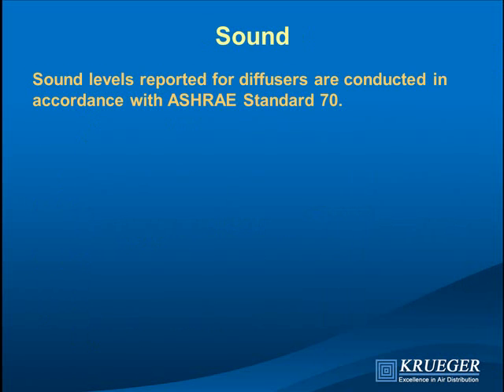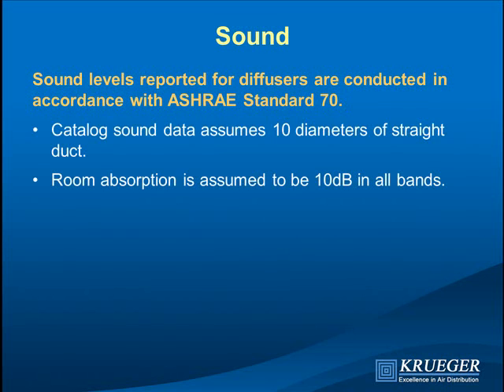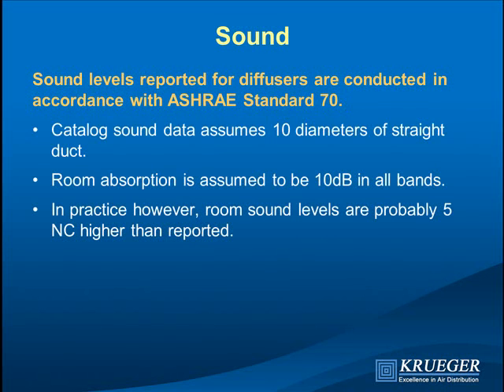For sound measurement, we use ASHRAE standard 70, which requires placing the device in a reverb room flush with the inside wall with 10 diameters of straight duct — so there's no inlet effect in our catalog data. We also assume 10 dB room absorption when calculating NC, which is probably not very realistic. A research study from the University of Nevada Las Vegas, reported in an April ASHRAE journal, recommends adding 5 NC to published data for everyone — not just Krueger — to account for inlet and room effects.